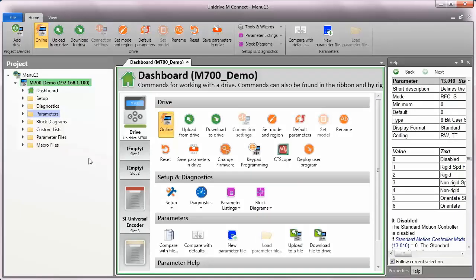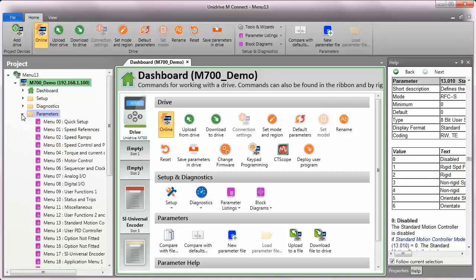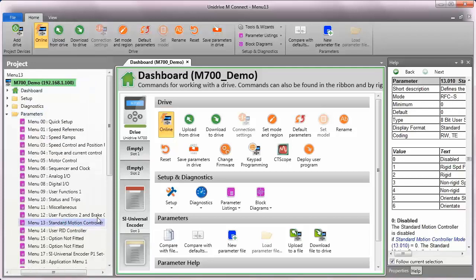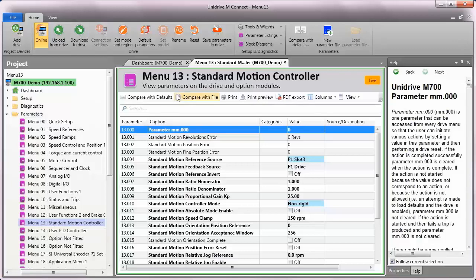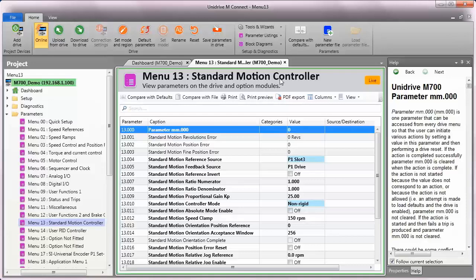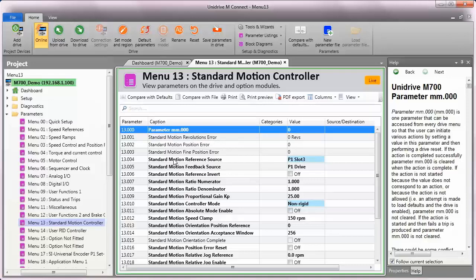Here I have MConnect software open, and I am connected to the drive. And we're going to have a look now at setting up menu 13. Menu 13 is in the parameters folder here, so I will double-click on this. Menu 13 is called the standard motion controller, and I should begin by explaining that. What we mean by standard motion controller, another word for it, is gearing. Menu 13 is used specifically to have the follower axis, which in our case is the lower conveyor here, follow a speed reference that's being generated by the encoder, which is attached to the upper conveyor. So standard motion controller is an alternative to using the advanced motion controller, the AMC, which is also built into the M700. Menu 13 has the advantage of being a little easier to use. So to begin, let's look at some of these parameters.